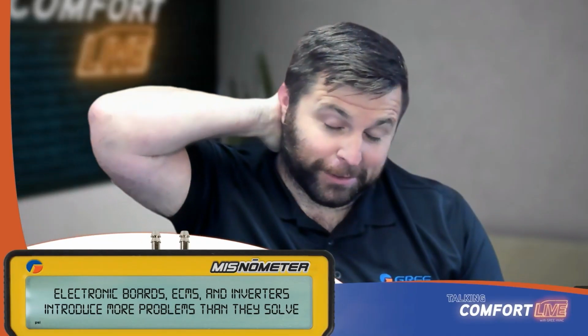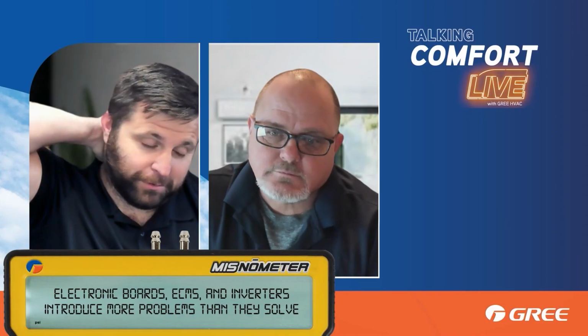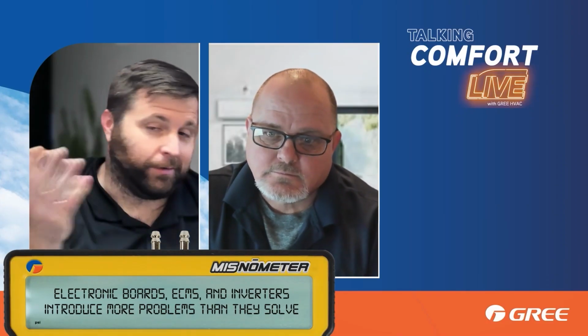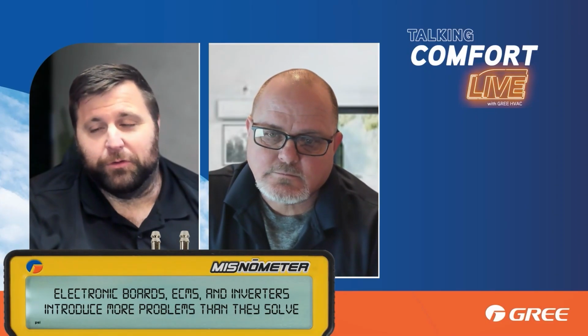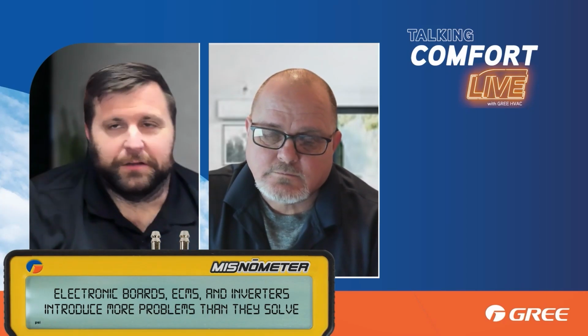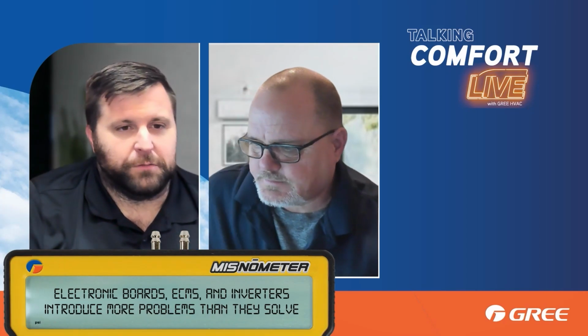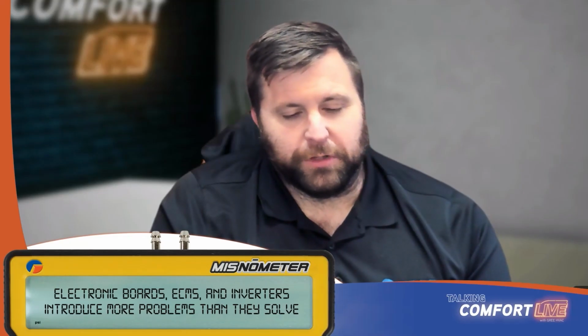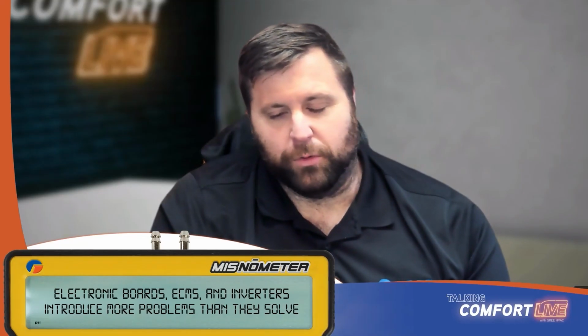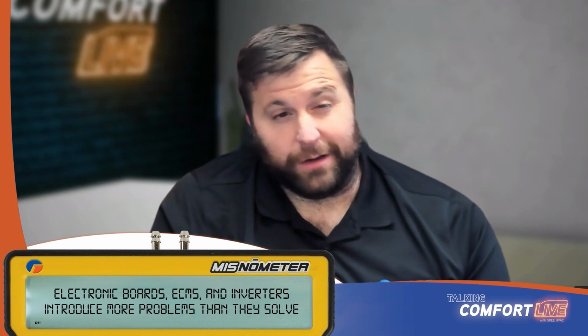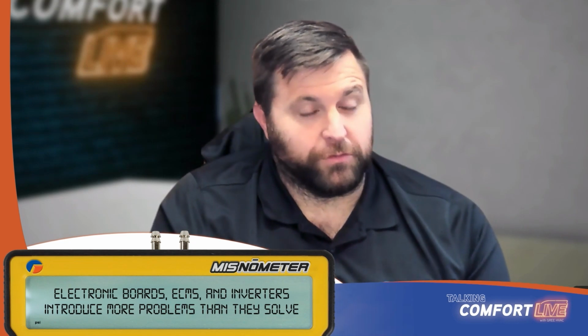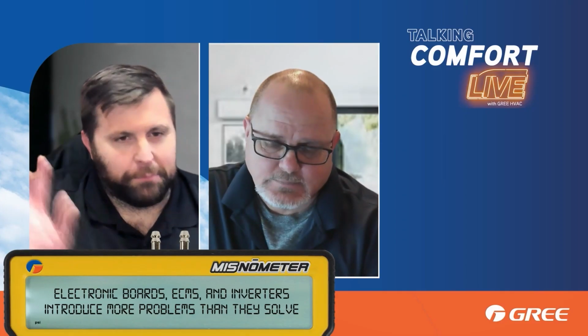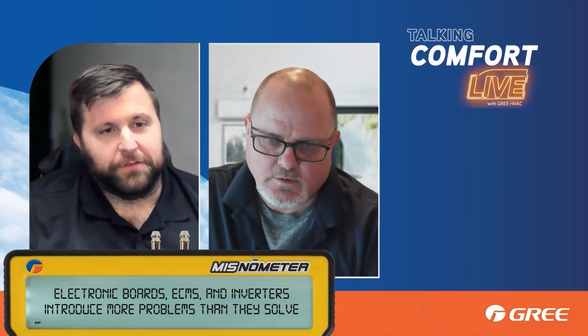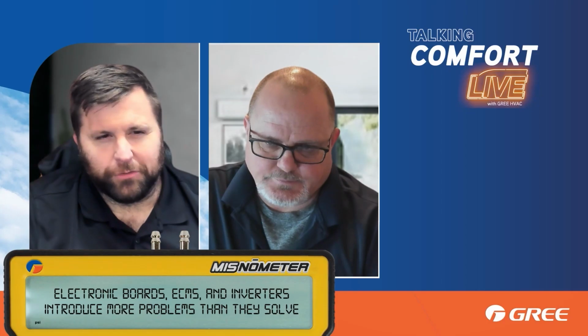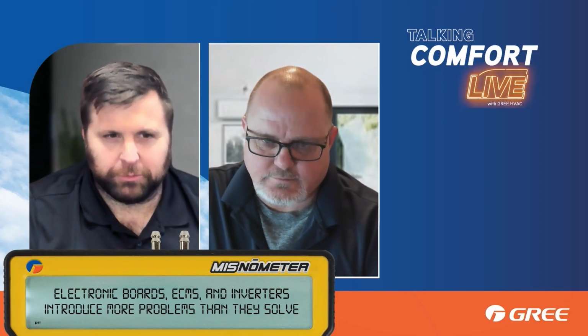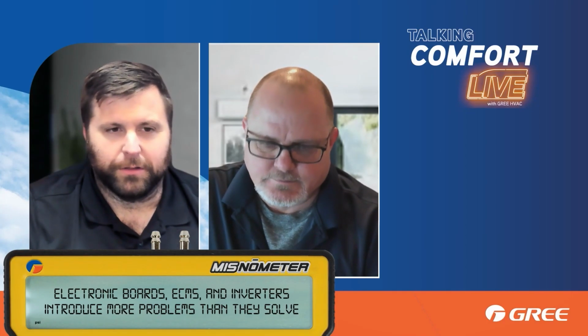I don't know why they did that, but that's actually something that's been used for a long time. Regardless, having to change out these boards, I've heard that from time to time as well. Talking about changing out a board, that's no different than changing out a defrost board. But if you've got a bad blower motor and it's an ECM motor, chances are what you're changing isn't the motor itself. It's probably just the ECM module in the back of it.